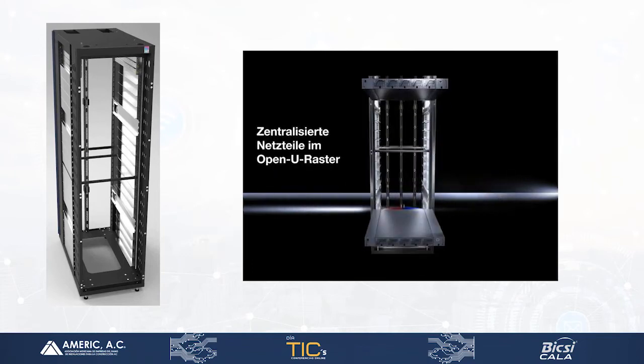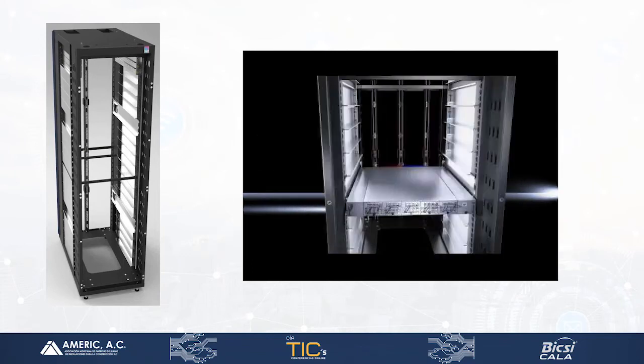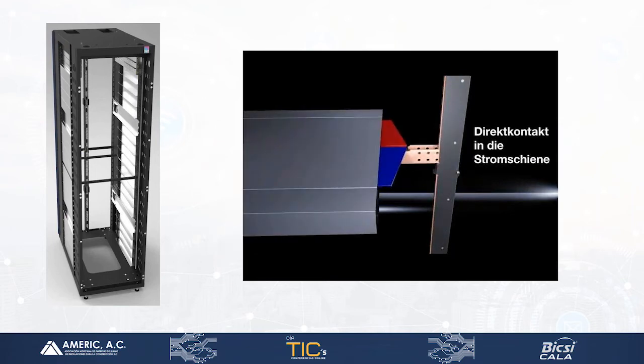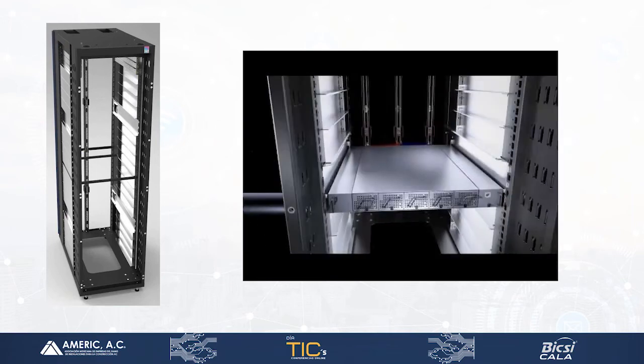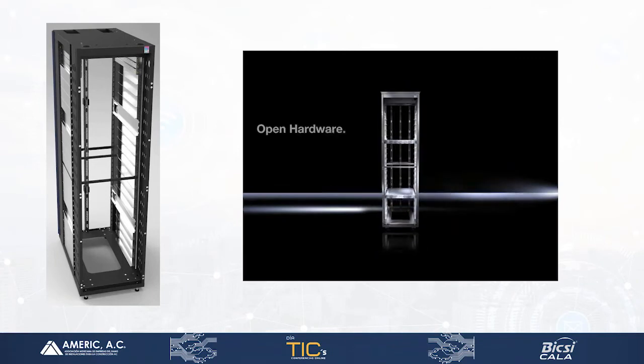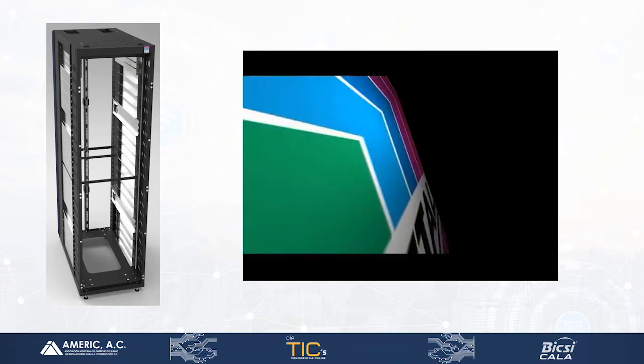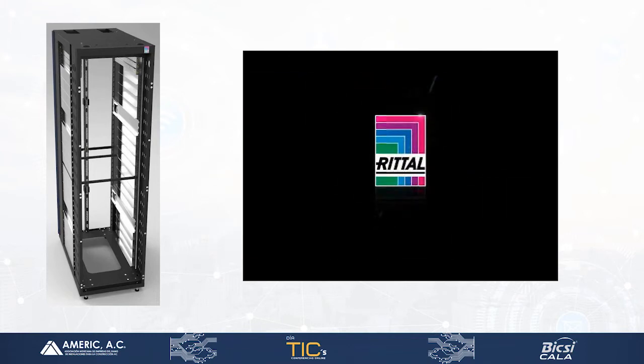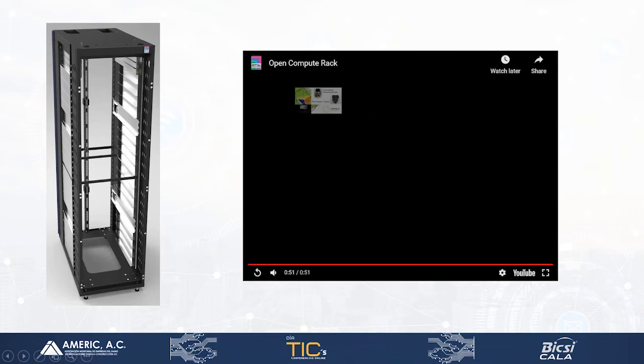And then we use these rectifier shelves, up to 18 kilowatts on a single U. This provides the DC feed from the 3-phase AC into the bus bar. So it's very, very simple. And that's why we don't need all the AC to DC power supplies inside the servers and equipment. Very simple.